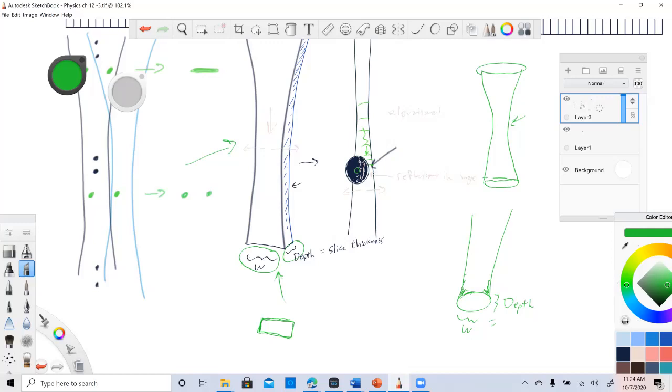But there are ways actually. We're going to learn in the next couple of pages, there are ways to focus the depth as well, because so far any increase in our resolution in the depth, or the elevational resolution, is more or less accidental, because we were focusing in the lateral resolution and the width of the beam, and it just happens to do a little bit better in the depth.